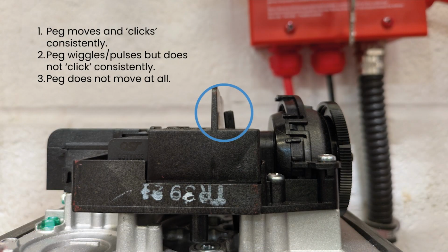Number 2. The pin wiggles or pulses but does not consistently make it to the end and hear the click. This indicates that the pump is spinning but is not generating sufficient flow. The most common solution for this is trapped air, and therefore venting would be recommended. But there can be other reasons which are covered later in this guide.